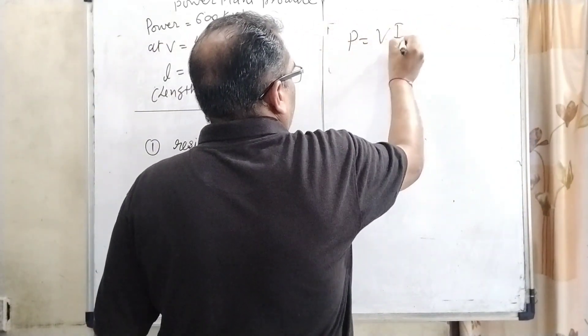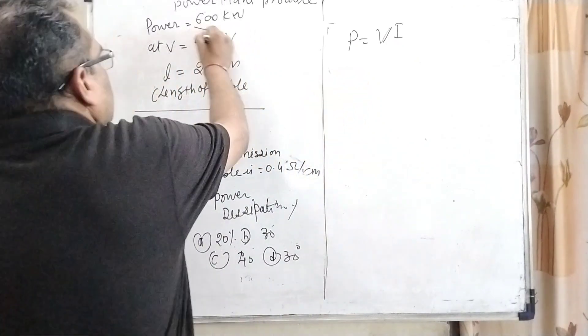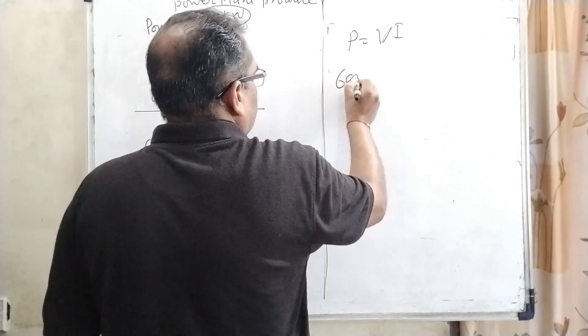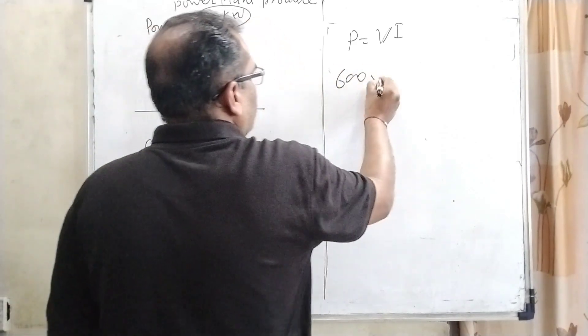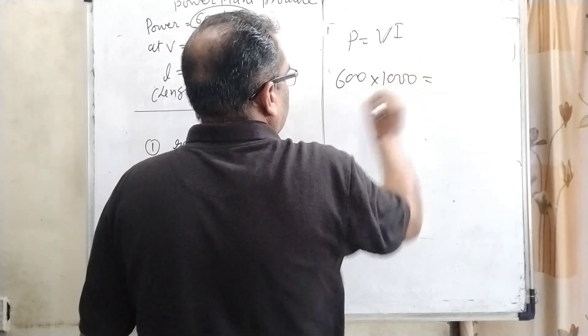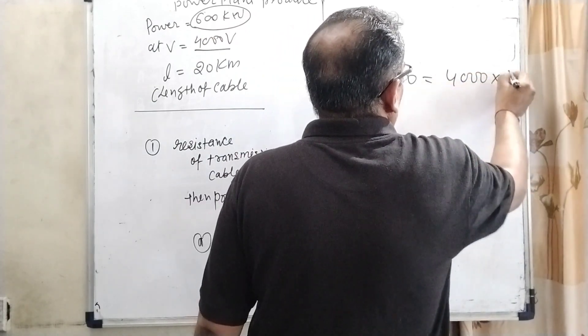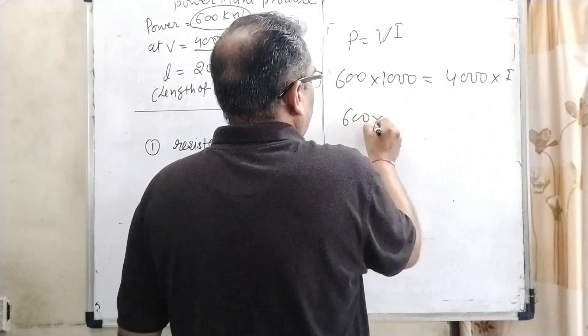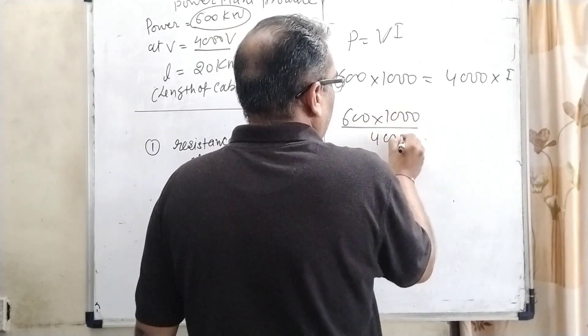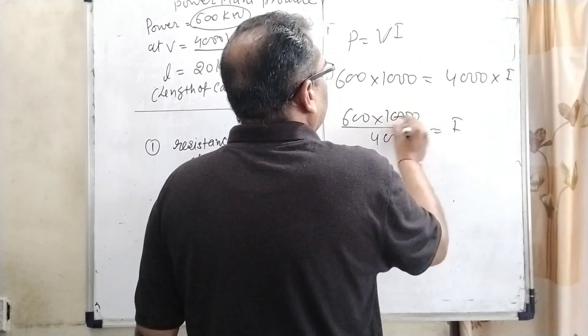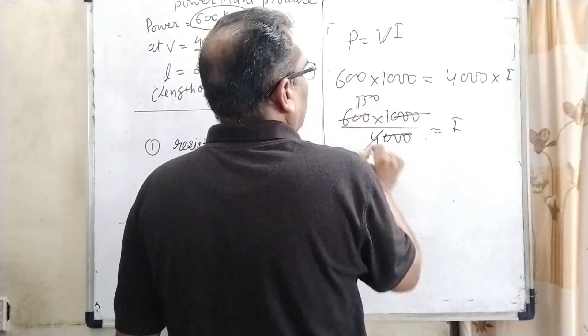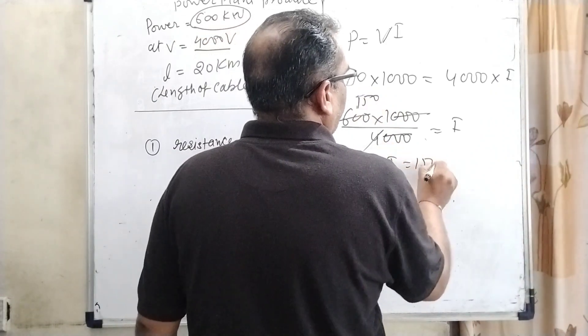First case we have given the direct transmission. In that case, power equal to V into I. Here V is potential and I is current. Here power is given 600 kilowatt means 600 into 1000. And potential is given 4000 volt, then 600,000 divided by 4000 that is 150. Here I equal to 150 ampere.